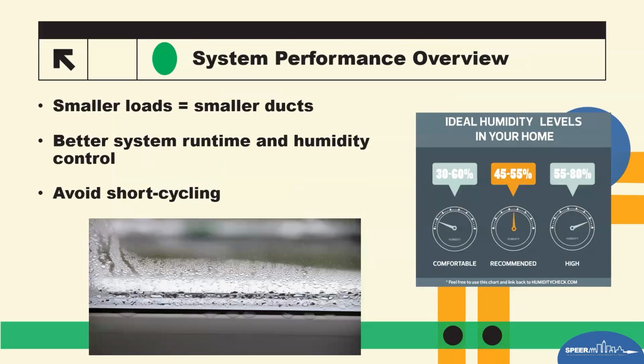And then, of course, speaking of humidity control, by having tighter houses and the system being correctly sized, meaning it has smaller loads and smaller duct systems, they run longer and it avoids short cycling. You can now eliminate some of that humidity that you see in older homes. A lot of times that picture you see at the bottom is just condensation on the inside of the windows. There's a lot of humidity trapped, and when it's hitting that cold surface, that happens a lot in cold climates up north, but we've seen it happen here in Texas a lot. What's the ideal humidity level inside of a house?